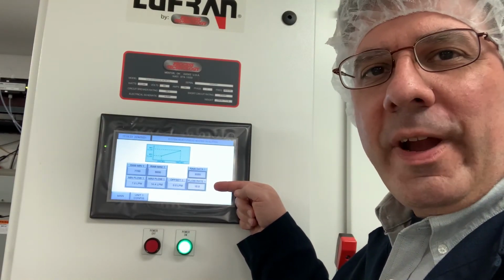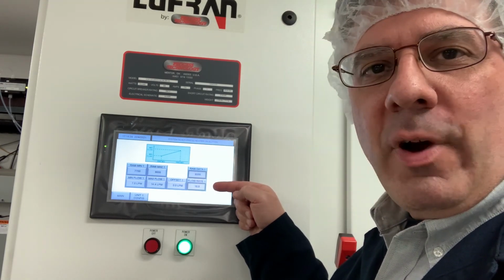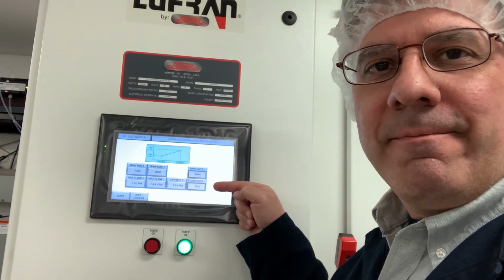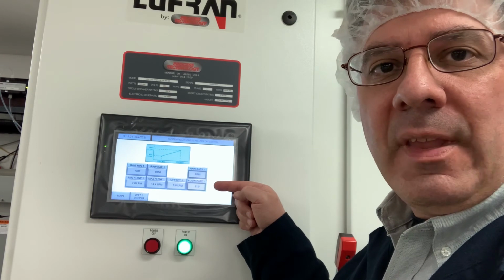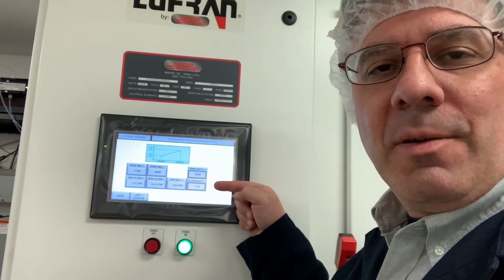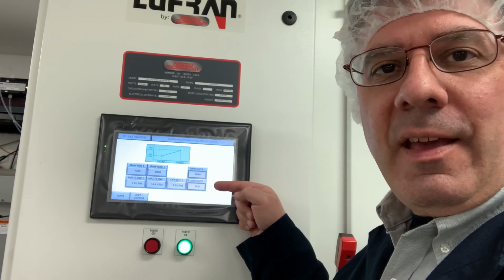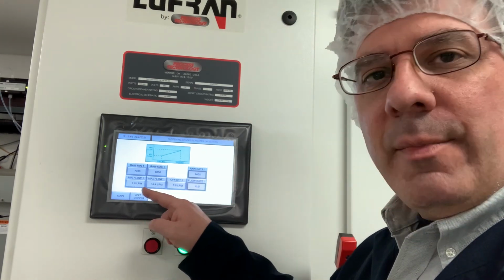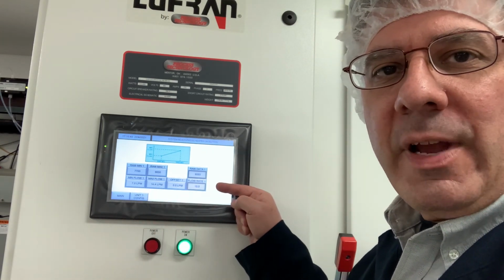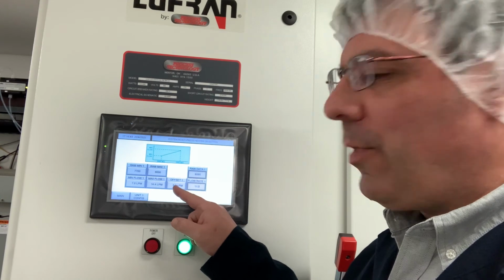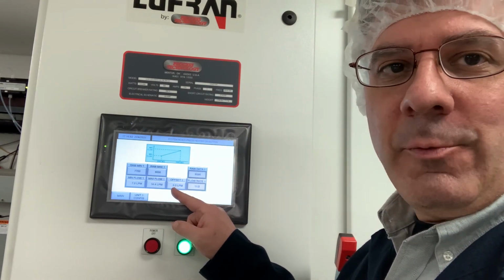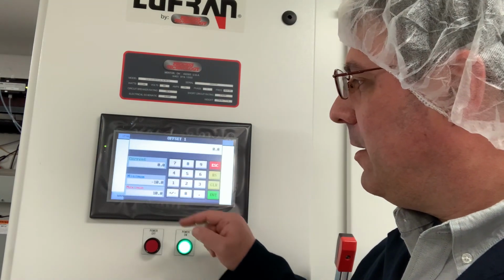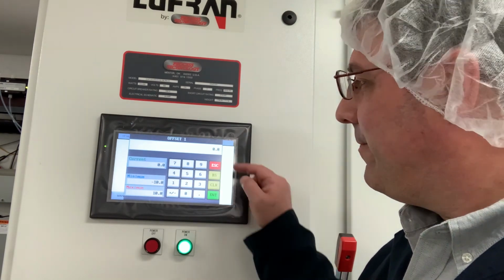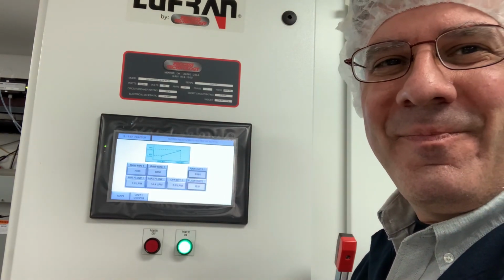Here you can see the flow rate. It's right around 10.8 to 11.0 liters a minute. So this is really close. This is considered a complete calibration. If after you adjusted the minimum and the maximum, you were still off in the middle range, that is where you would want to make an adjustment to your offset, which is this button right here. Fortunately, in this case, we don't need to.